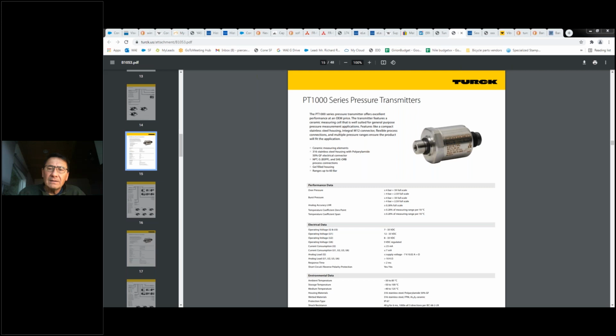And the main bugaboo about these sensors is making sure that the field wiring is secure, number one. And number two, that you bear in mind that the signal is a low voltage, low current signal, certainly subject to some interference, especially if you're using it in the neighborhood of a variable frequency drive, in which case the variable frequency drive is probably the worst case noise source. And that sort of noise overlay from the 700 volt spikes on the output of the VFD tends to disrupt the amplitude of the pressure sensor signal coming back.